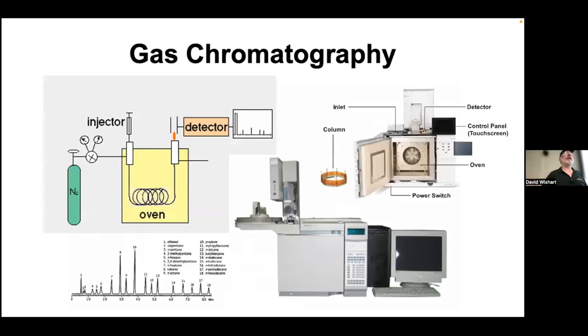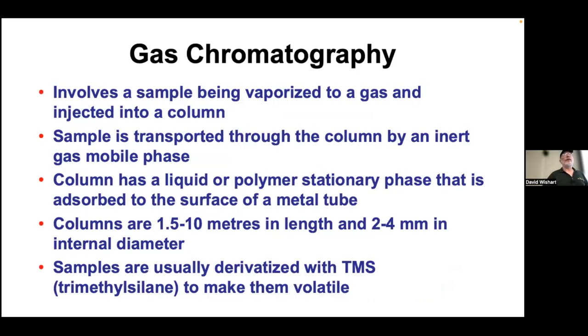There's another technique where the mobile phase isn't water or acetonitrile — it's a gas, usually helium — and instead of running at room temperature, things run in an oven. This is gas chromatography, or GC. Like an HPLC system, you have an injector, but instead of a pump pushing liquid, you have a gas tank. Things pass through a coiled column — very tiny and long — in an oven, then go to a detector. Detectors include flame ionization or a mass spectrometer.